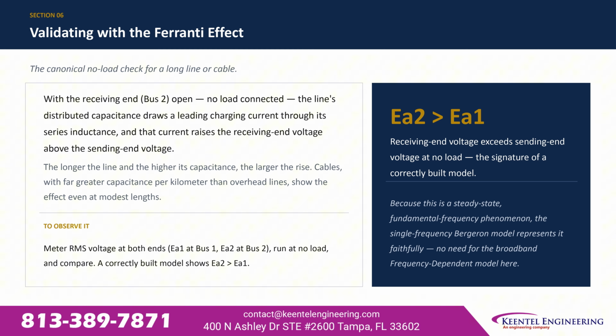That current raises the receiving end voltage above the sending end voltage. The longer the line and the higher its capacitance, the larger the rise. Cables with far greater capacitance per kilometer than overhead lines show the effect at much shorter lengths.